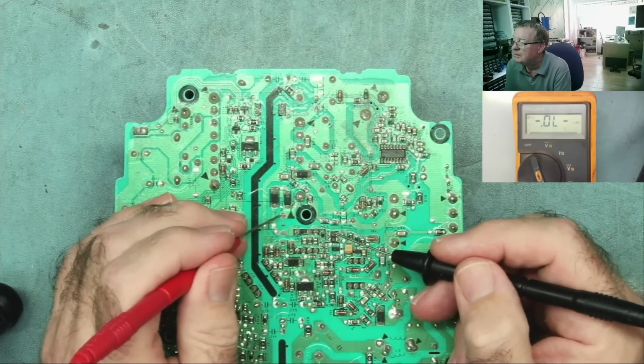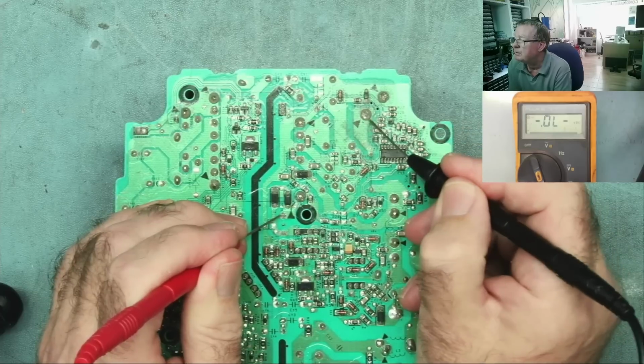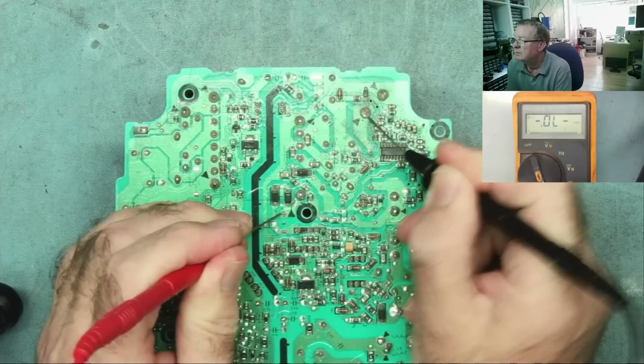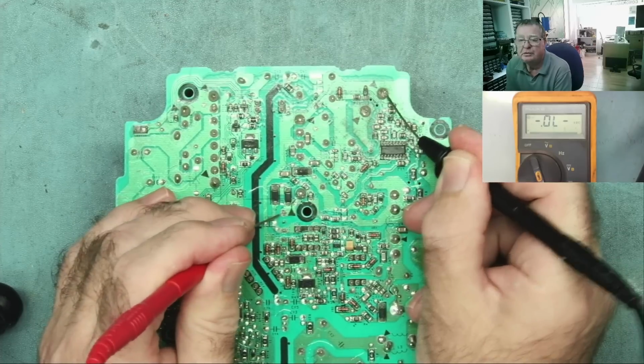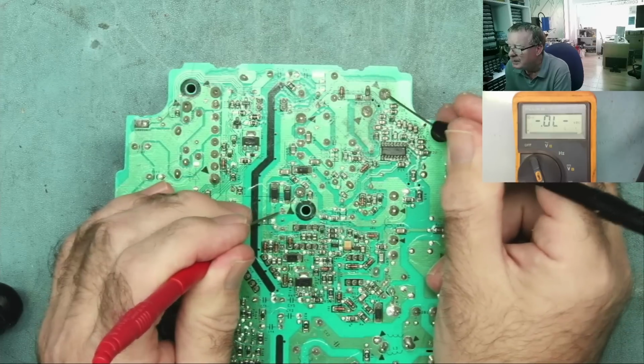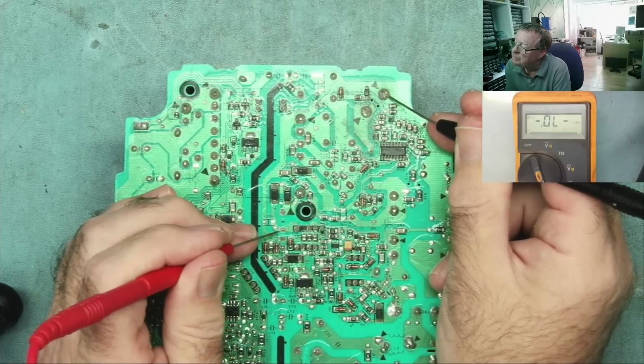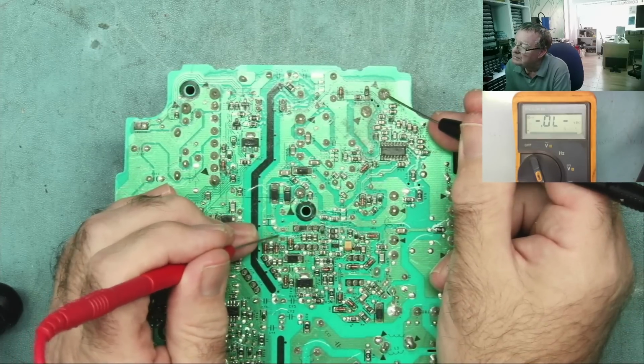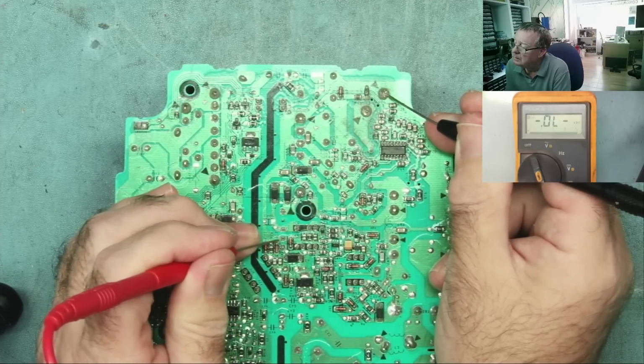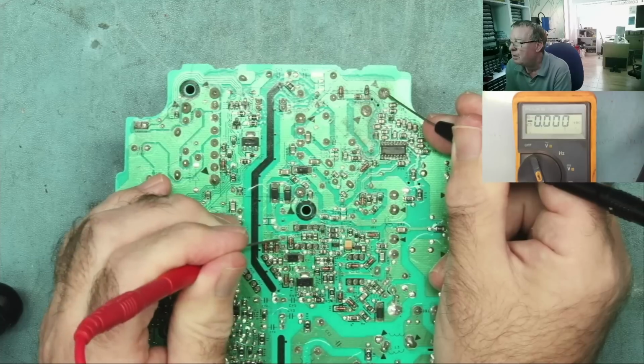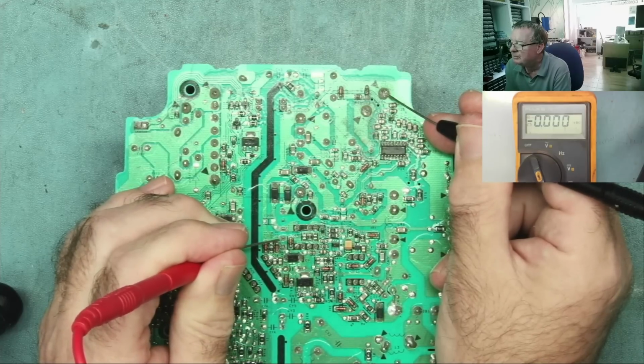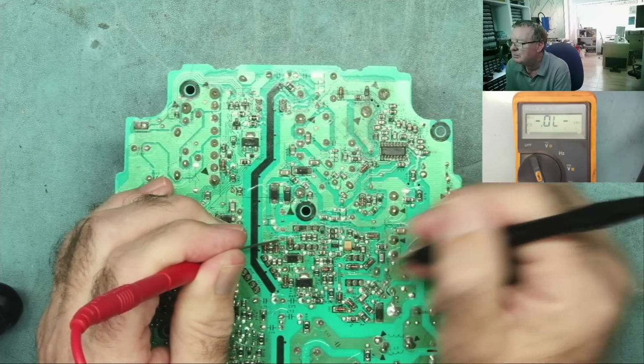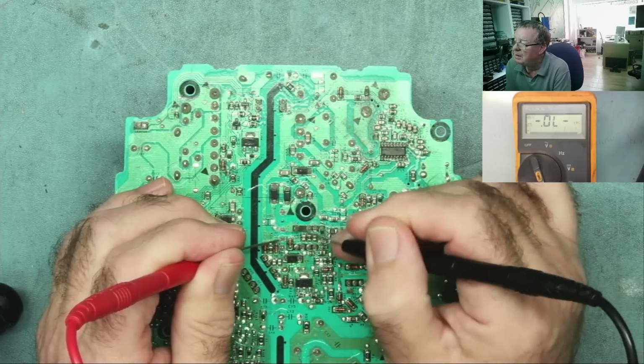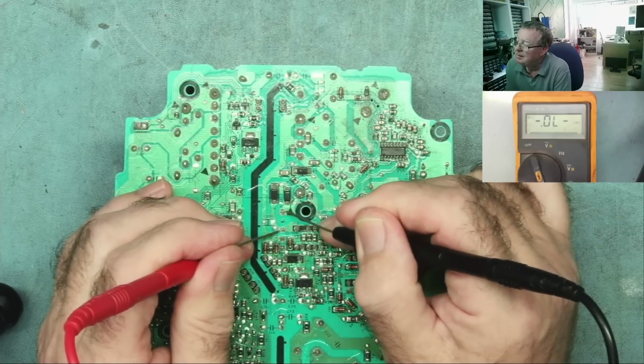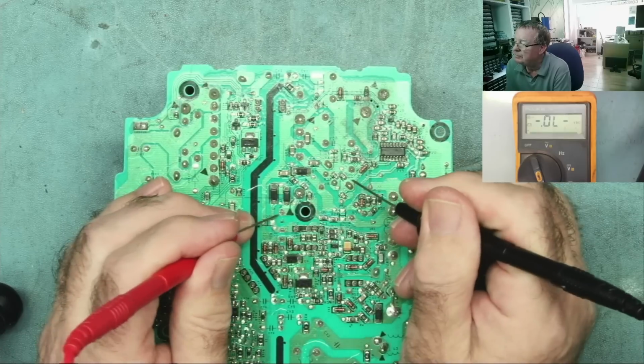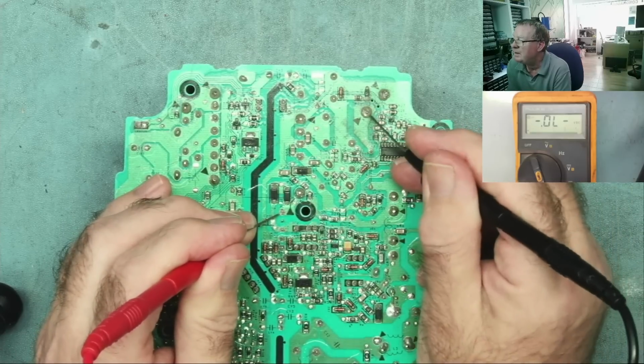From the other end of this winding, this is where we would expect to go to the positive of here. It doesn't, right? Nor does it go to hot ground, where we would not expect it to go. But we do know that the other winding, this little secondary, this end goes to hot ground, and that's how we drew that schematic out, roughly how it's connected. So that is the auxiliary winding, this is the primary winding. The winding itself is okay, but I don't have a connection from here to here.